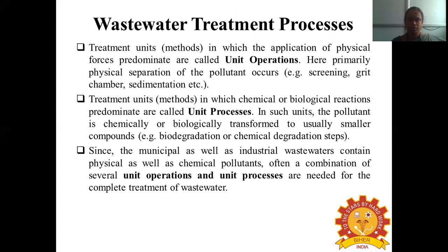Let us see what the wastewater treatment processes are. Mainly, they are technically called unit operations and unit processes. Treatment units in which the application of physical forces predominate are called unit operations — like screening, grit chamber for removal of grit, sedimentation process, etc. Treatment units in which chemical or biological reactions predominate are called unit processes, where the pollutant is chemically or biologically transformed into smaller degradable compounds, e.g., biodegradation or chemical degradation.